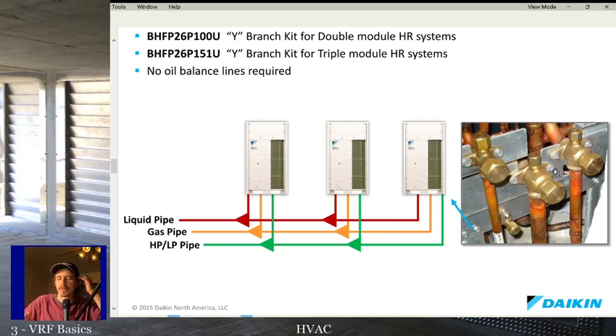It's critical you understand the manufacturer instructions because mini splits, for instance, have a distance you have to be from walls, and especially a distance you have to be from a ceiling. I remember for a while there, I would do a lot of Daikin mini splits because they had a very small clearance that the manufacturer required to the ceiling as opposed to some other units. And you need to know what their required clearances are. You need to know if you're going to duct a mini split, the small ducted ones, what their static pressure capabilities are because they're relatively low.